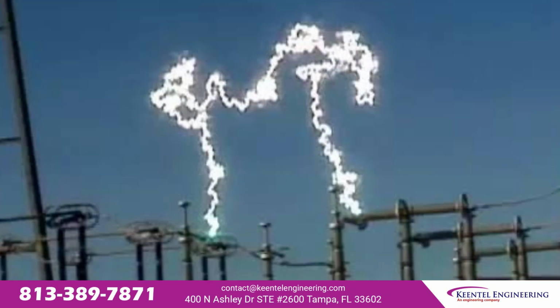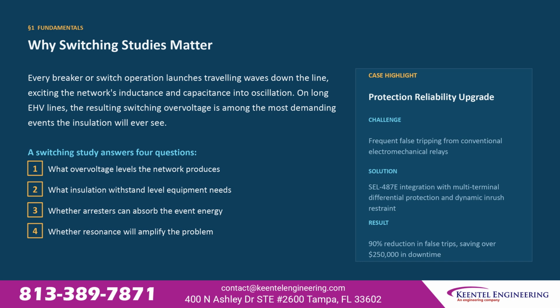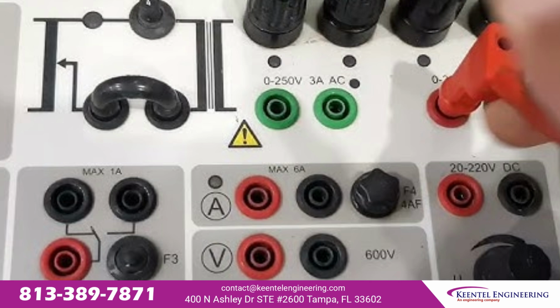These answers drive arrestor ratings, breaker pre-insertion resistor decisions, and the basic insulation level specified for transformers and line equipment. Getting them wrong means either underspecified equipment that fails in service or overspecified equipment that costs more than it should. A switching study turns those risks into specified, traceable numbers.